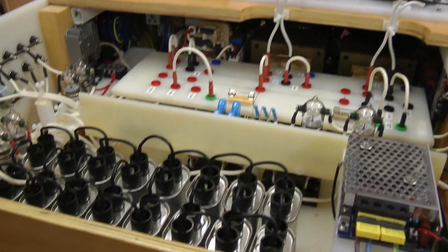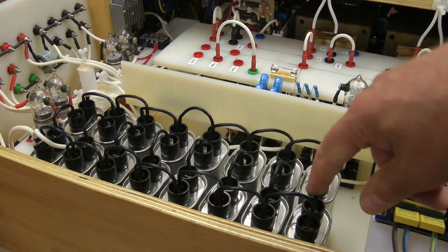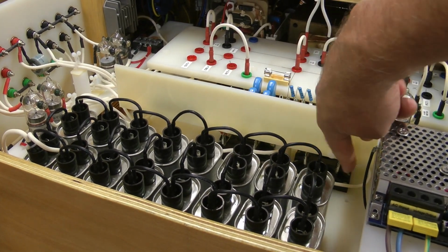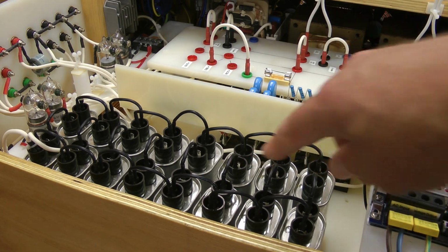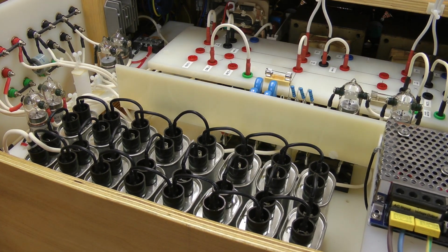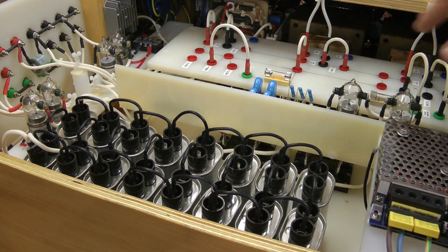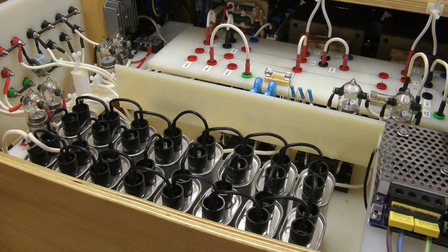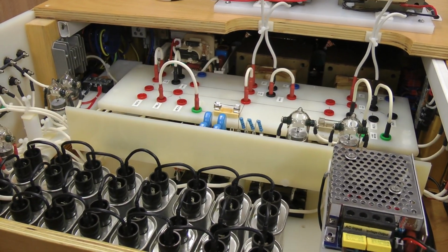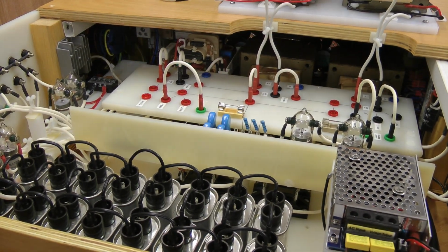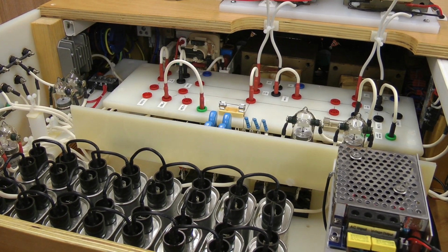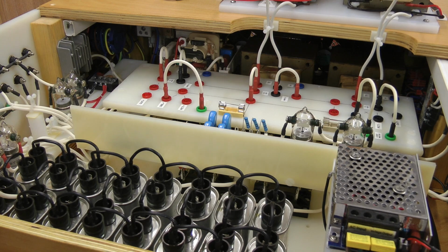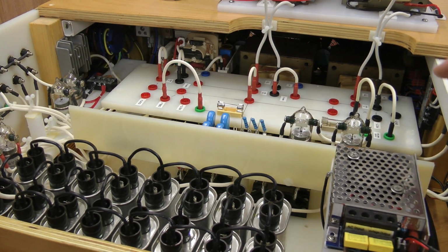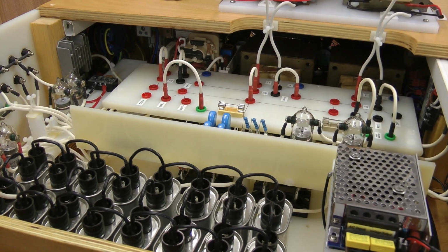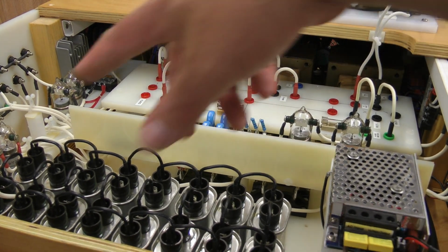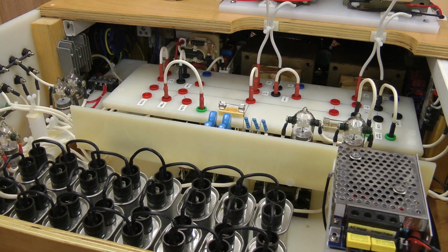Here is the level shifter with the diodes underneath. It's a 4 microfarad level shifter, and open circuit it will take the 6 kilovolts from the two series-connected transformers up to, in principle, 12 kilovolts, though about 11 kilovolts is what you actually measure. Fully loaded that comes down, since the transformers produce just over 2 kilovolts each, so with the 4 and 8 fully loaded you could get to about 7 kilovolts.